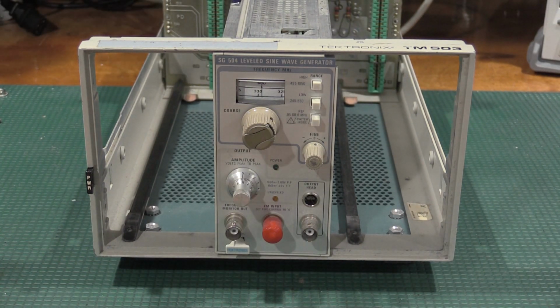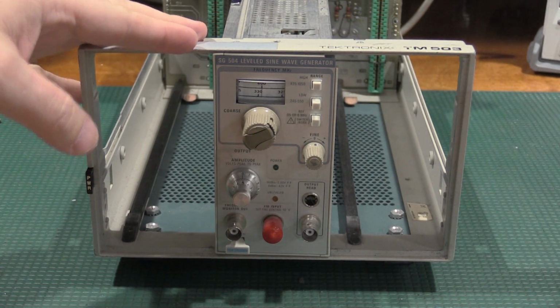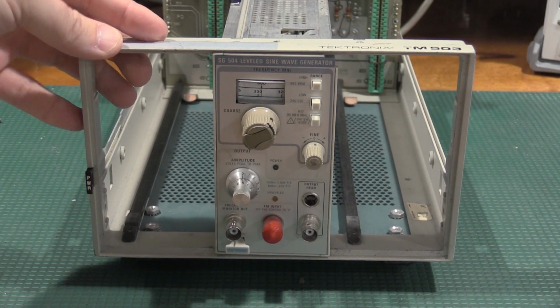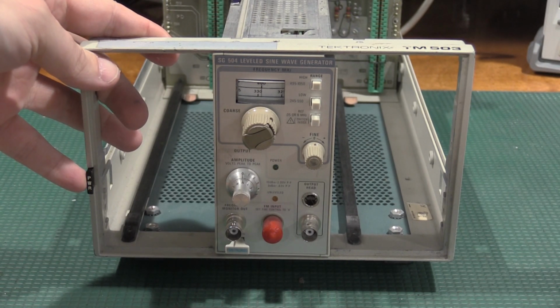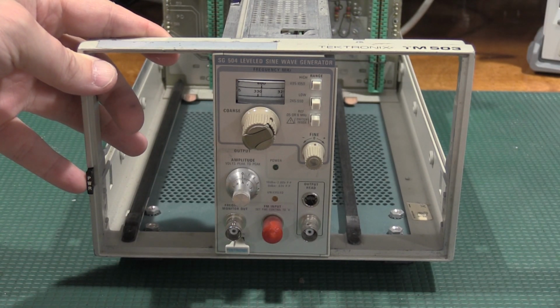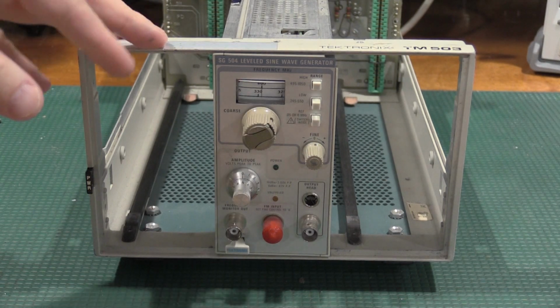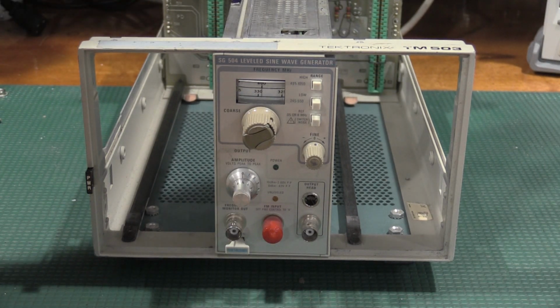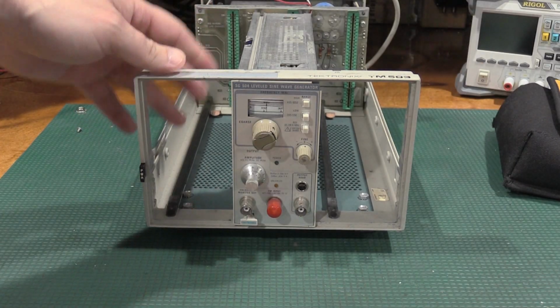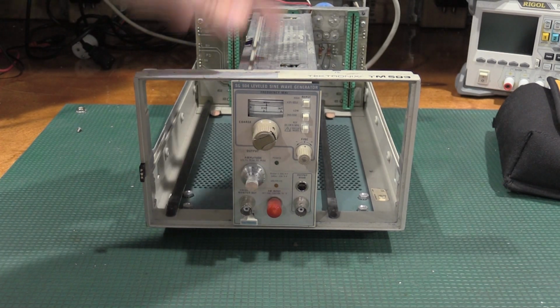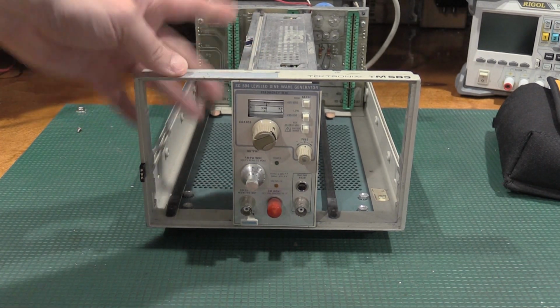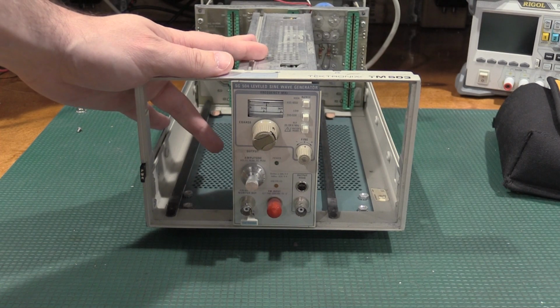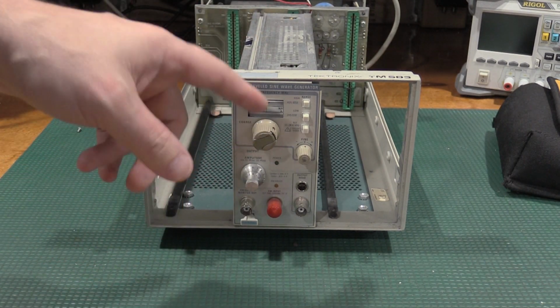Today on the bench is my SG504. This is the high frequency signal generator from Tektronix. It's a TM500 plug-in. I was starting to work on my 7904A, recording a video for that, and going through the necessary calibration equipment, I found I needed this unit. So I have to repair this unit. I know there's a fault on this one.